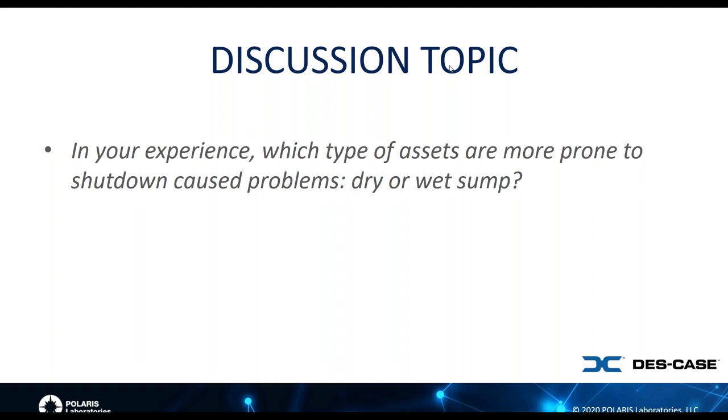I would agree with you in general. I mean, you can always think of scenarios where a dry sump would be a challenge. But with a dry sump system, you always have an opportunity to apply some degree of filtration on the oil in the reservoir before you start it back up. If you follow proper startup procedures of getting the oil flowing at the right rate before you start up the machine and apply load to the machine, then you can mitigate a lot of that.